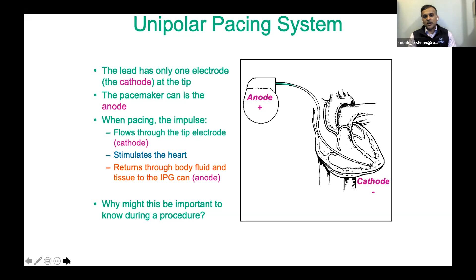So when you take the pulse generator out of the pocket, it's now exposed to air, and the current can't go through air to finish the circuit, so you'll lose pacing. Another trick you can do here is either you place a temporary pacemaker if you need to, or you wrap the pacemaker pulse generator in a lap or a sponge that's wet, and the half of the pulse generator is outside of the body, but the wet lap is placed partially inside of the pocket. That will still form the circuit, and you'll be able to keep pacing going without losing pacing. So that's a little tip and a trick to keep a unipolar pacing system continuing to pace even when physically the device is outside of the pocket.